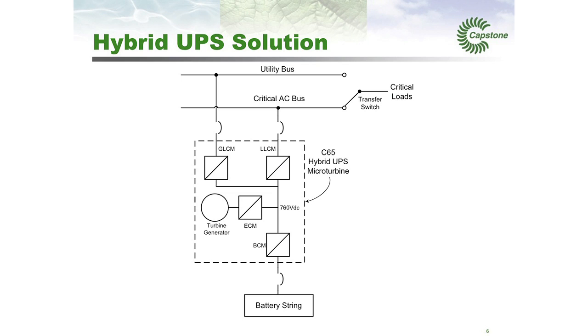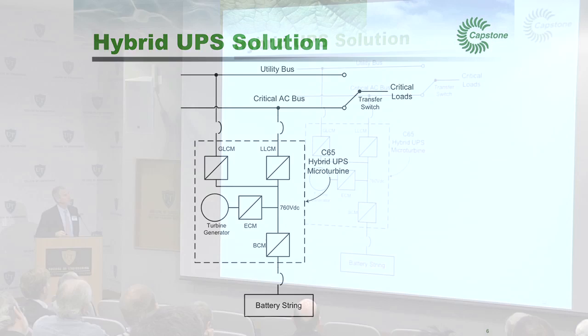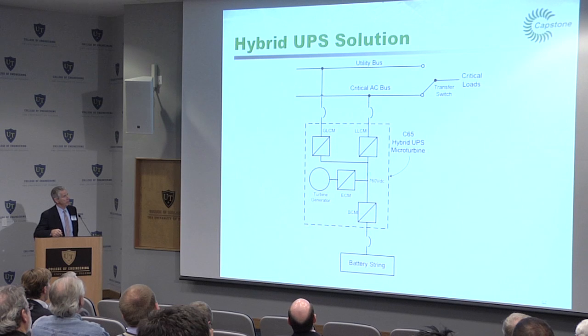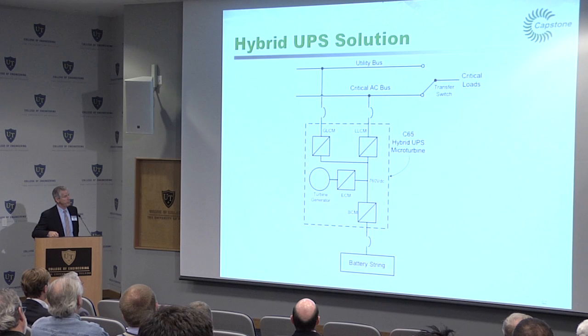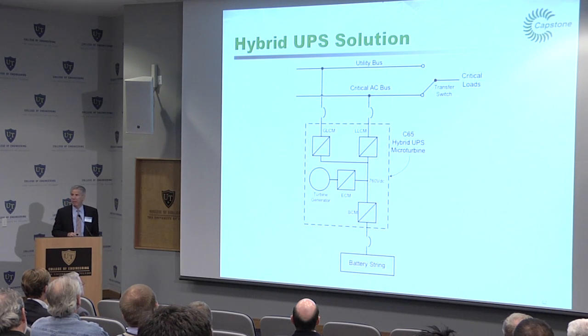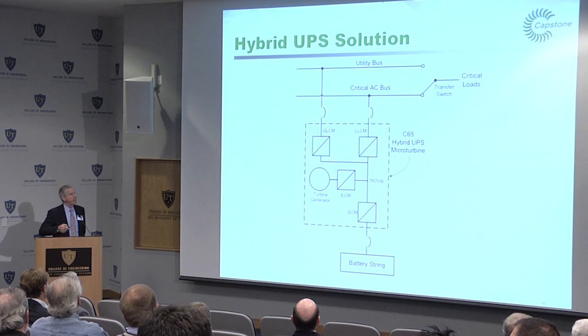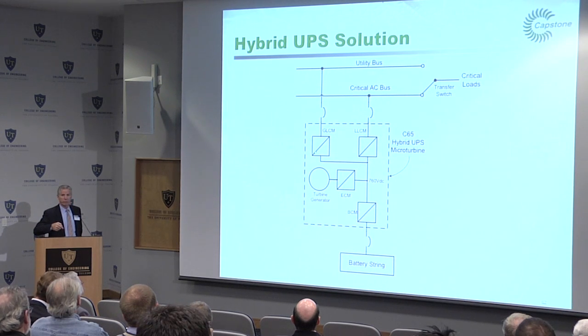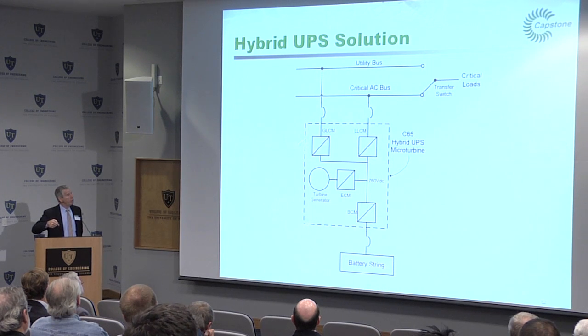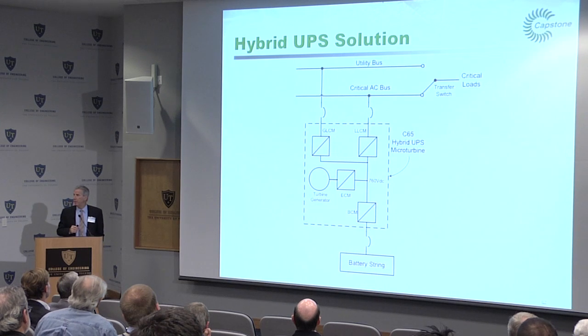Remember the picture from before? We have a power electronics module, called a load control module, that takes our DC bus and makes it available as AC power to the load. We have our turbine generator module to convert high frequency AC to DC, and another DC to DC module that gets you down to a battery. We already have all the pieces, so we just add one more load control module, connect it to the utility source, and now we have what we call our hybrid UPS system.